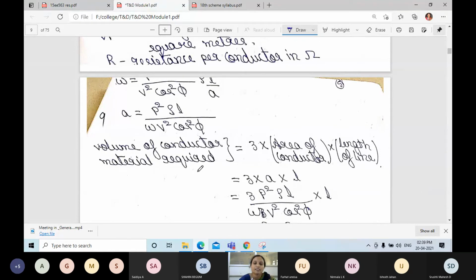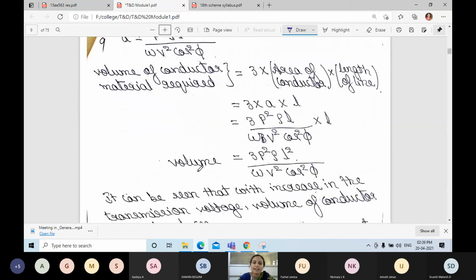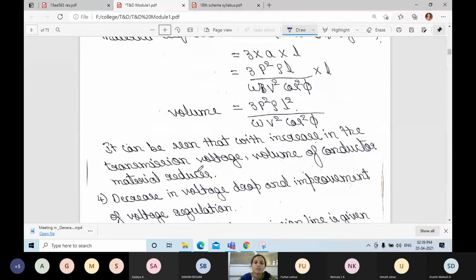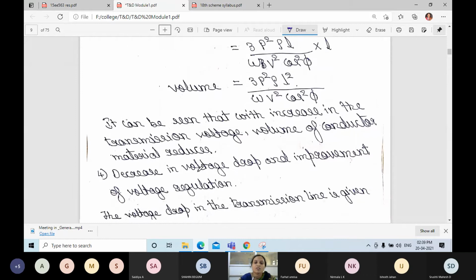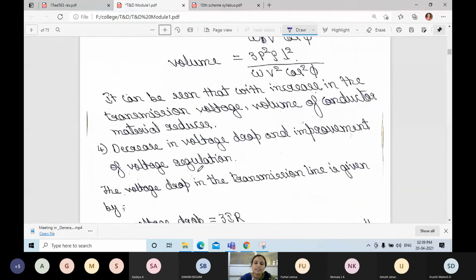The area of the conductor we got is A is equal to P square rho L divided by W V square cos square phi. Substituting that, the volume equation is 3 P square rho L square divided by W V square cos square phi. Here also V is inversely proportional. So if we increase the voltage level, the volume of the conductor material will be reduced and the cost will be reduced. This is the third advantage.